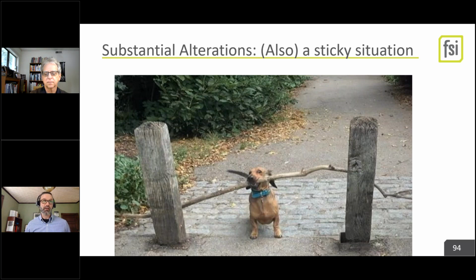So there's a whole discussion about a major planned upgrade. And depending on what heat pump system you decide to go to, maybe it's not hydronic, maybe it's air side, and maybe it doesn't run down to super low temperatures and you need electric resistance backup, you likely will end up with a higher electrical load on your building than you had previous to the upgrade. You know, chillers aside, it can trade off, but generally speaking, if you need electric resistance backup, it'll be a bigger electric load. So there's a whole discussion to get into with your MEP team, again, early, about what do we need and do I need to upgrade the building electrical service to meet this or not? It's all very much it depends.